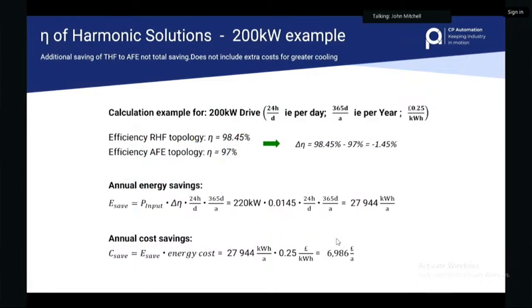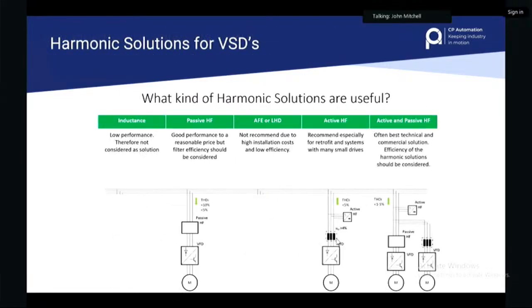This is a prime example, just for reading later on. One customer chose between two different technologies, comparing a 200 kilowatt VSD against another. The figure shows the efficiency difference between the two solutions. That saved them £7,000 a year just in inefficiencies. That's a technology choice, nothing to do with operational factors. You can read that yourselves later on.